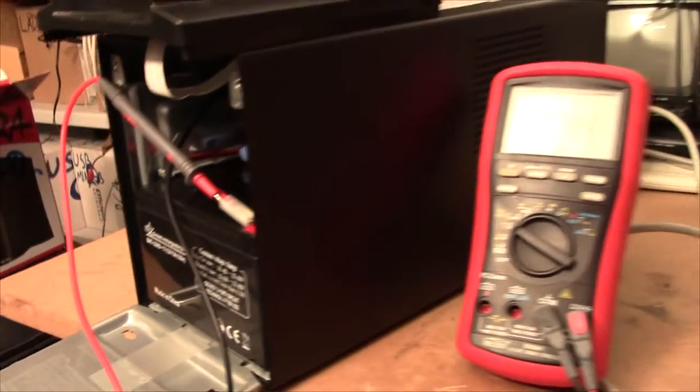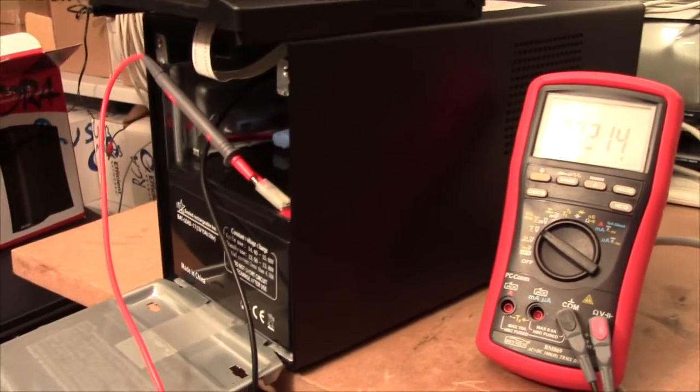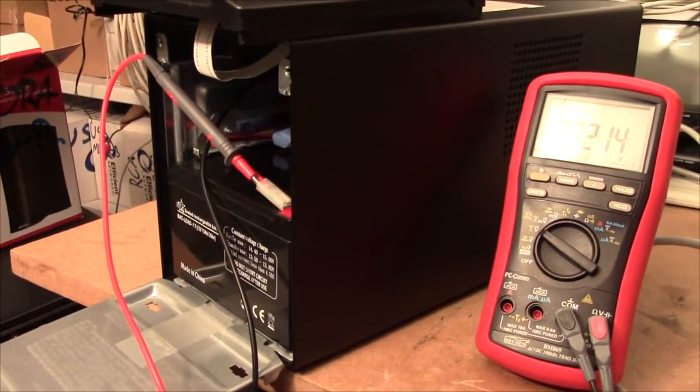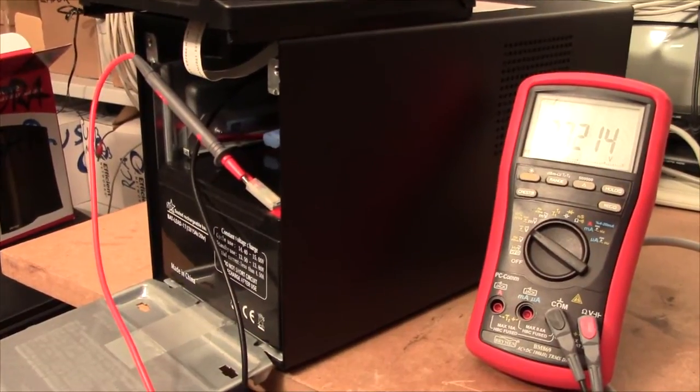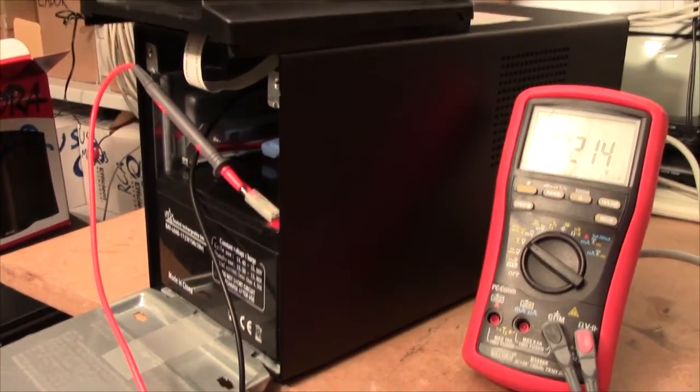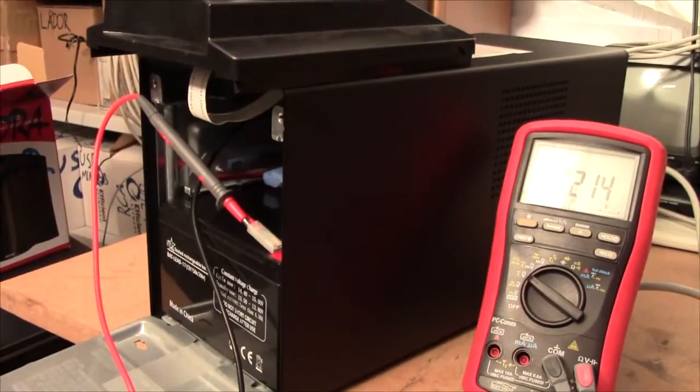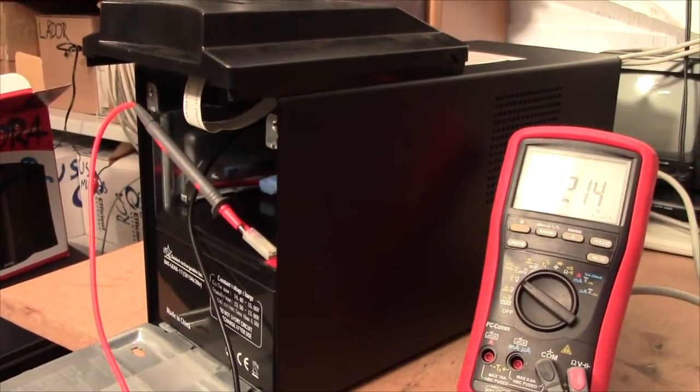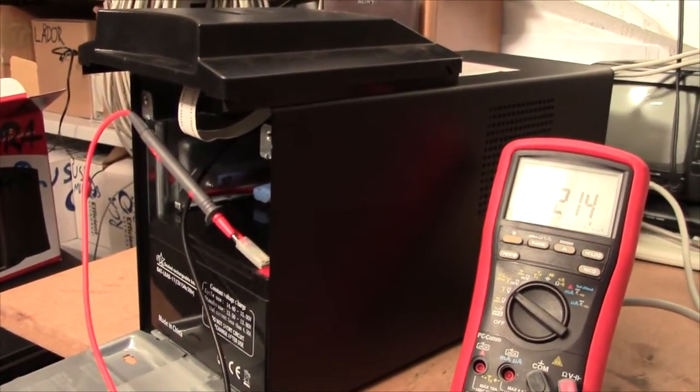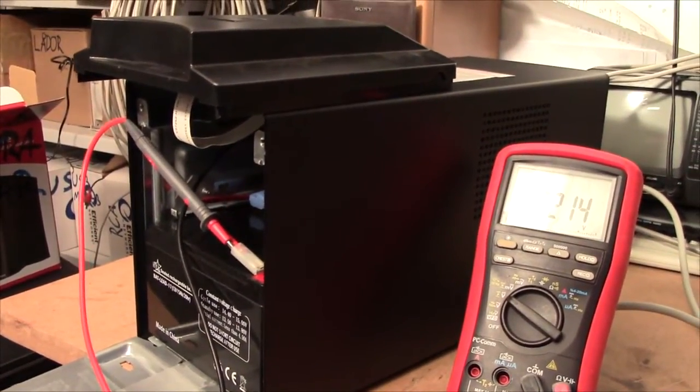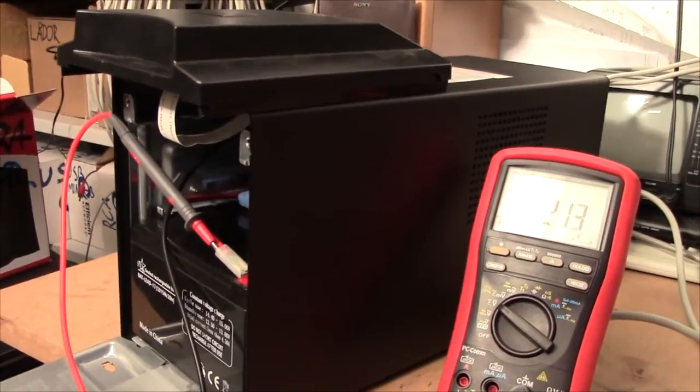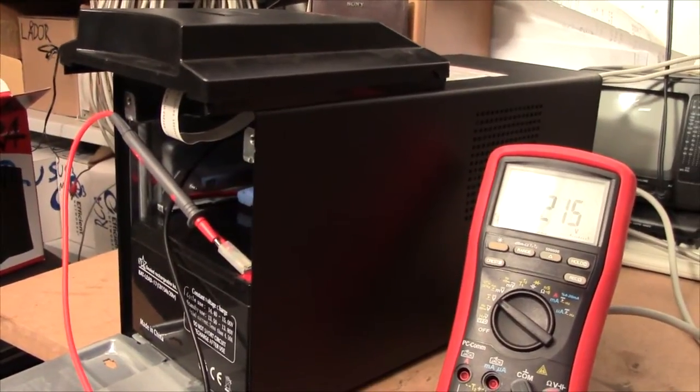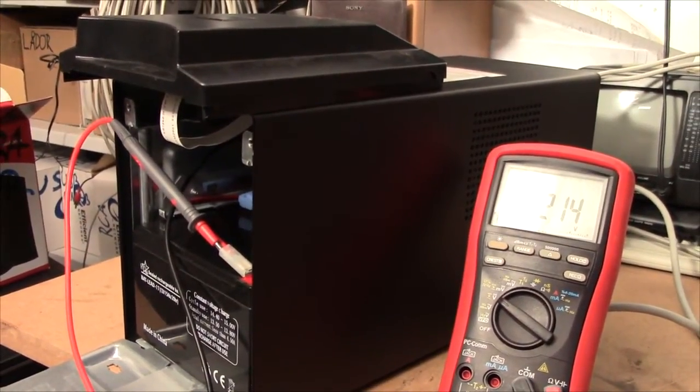So, these units usually ship with two 12Ah batteries, and I've adjusted the battery constant to essentially just a little bit more than the original. I think that with a 500W load, it's supposed to run for 9 minutes, and I adjusted the battery constant to say that it's going to run for 15 minutes.